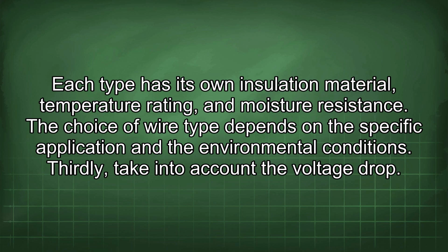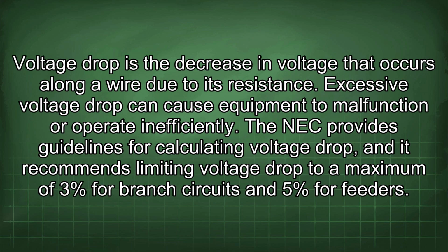Thirdly, take into account the voltage drop. Voltage drop is the decrease in voltage that occurs along a wire due to its resistance. Excessive voltage drop can cause equipment to malfunction or operate inefficiently. The NEC provides guidelines for calculating voltage drop, and it recommends limiting voltage drop to a maximum of 3% for branch circuits and 5% for feeders.